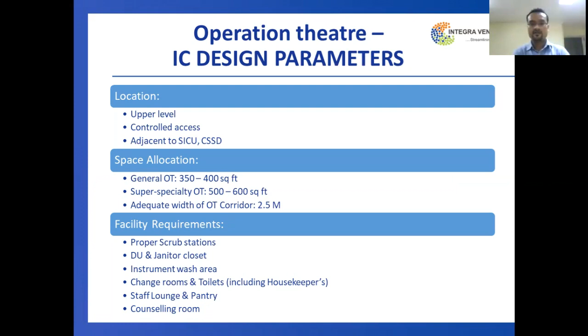Now, while designing the operation theater complex, we usually comply with the zoning requirements. We have already spoken about the three areas: protective zone, clean zone, and sterile zone. In the sterile zone, we have the operating rooms and scrub stations adjacent to the operating rooms, so that just after scrubbing, the doctors or other staff can get inside the operating room. We also need the sterile store, with sterilized material adjacent to the operating room in the sterile zone.